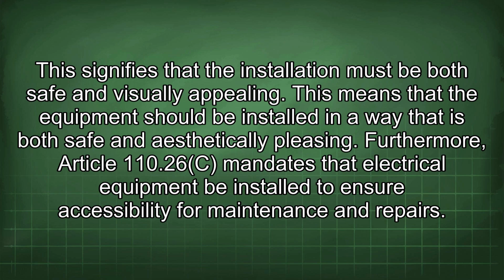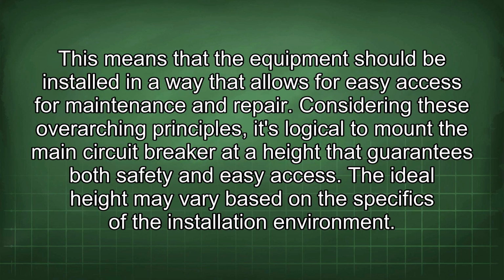Furthermore, Article 110.26c mandates that electrical equipment be installed to ensure accessibility for maintenance and repairs. This means that the equipment should be installed in a way that allows for easy access for maintenance and repair. Considering these overarching principles, it's logical to mount the main circuit breaker at a height that guarantees both safety and easy access. The ideal height may vary based on the specifics of the installation environment.